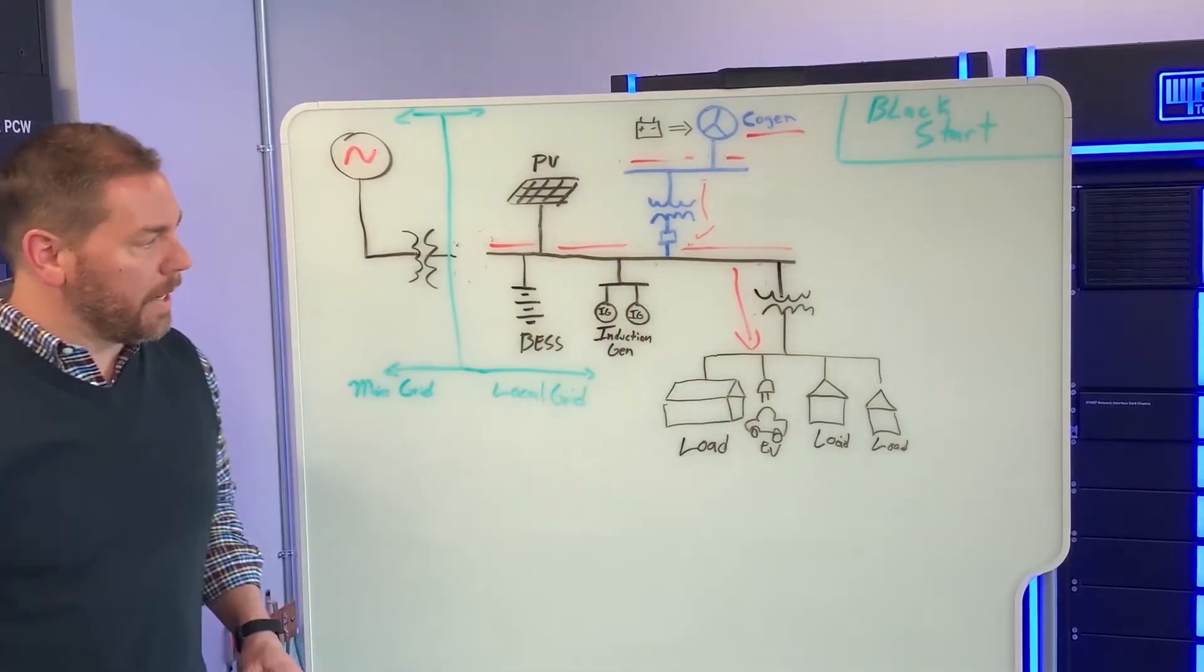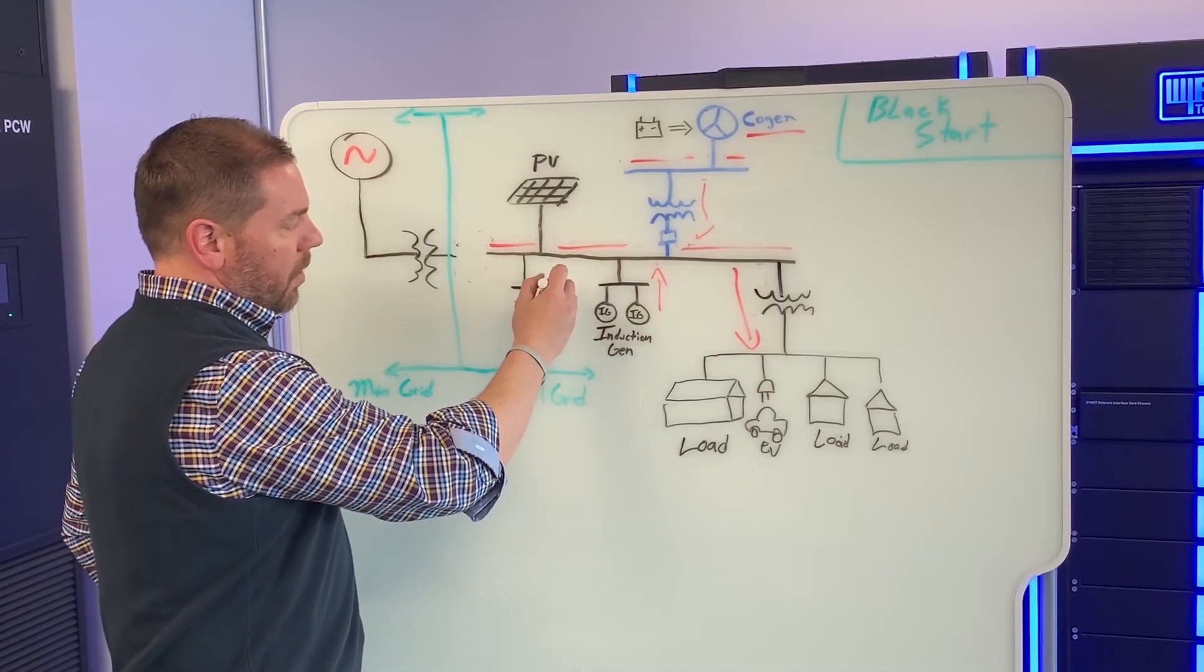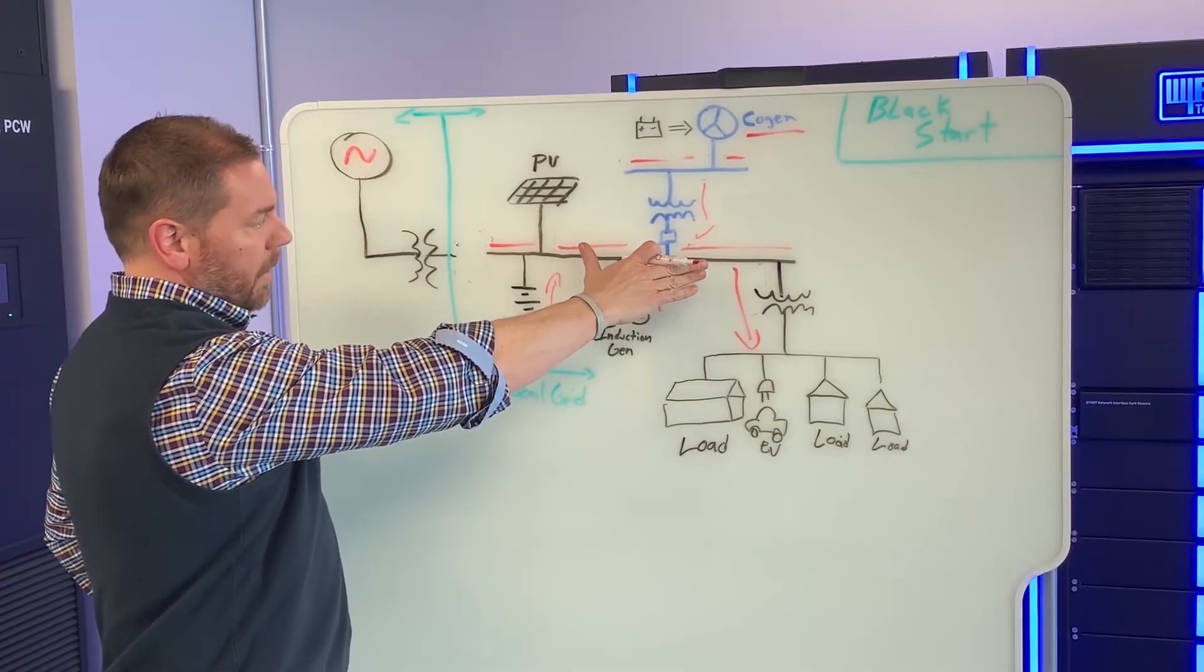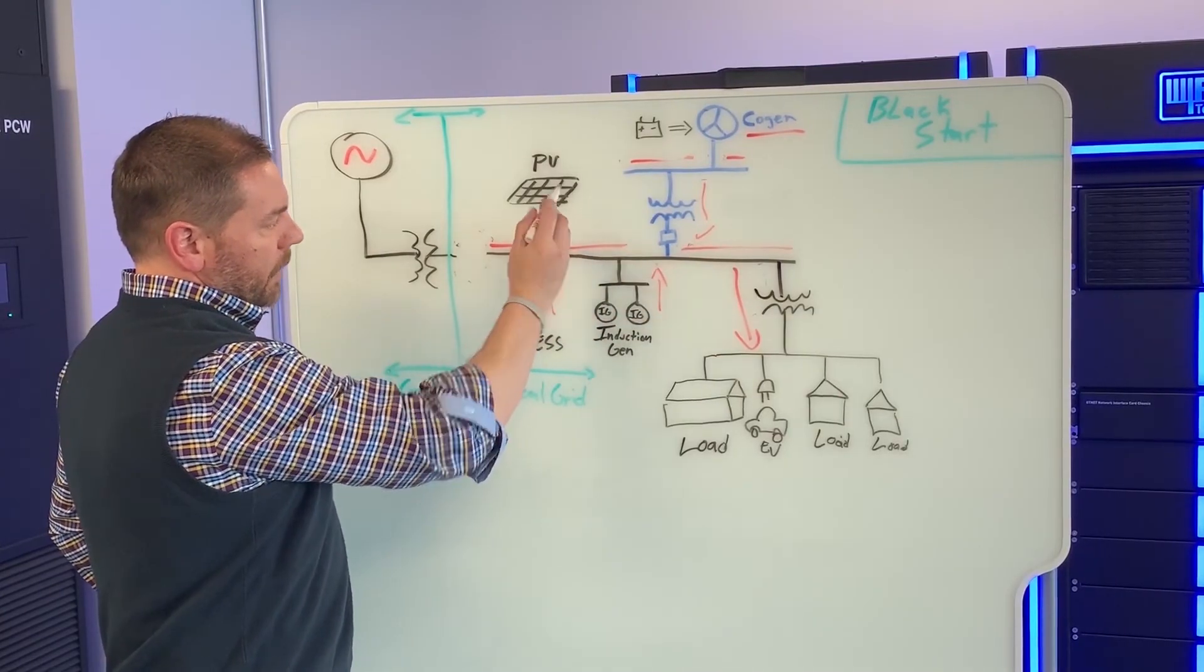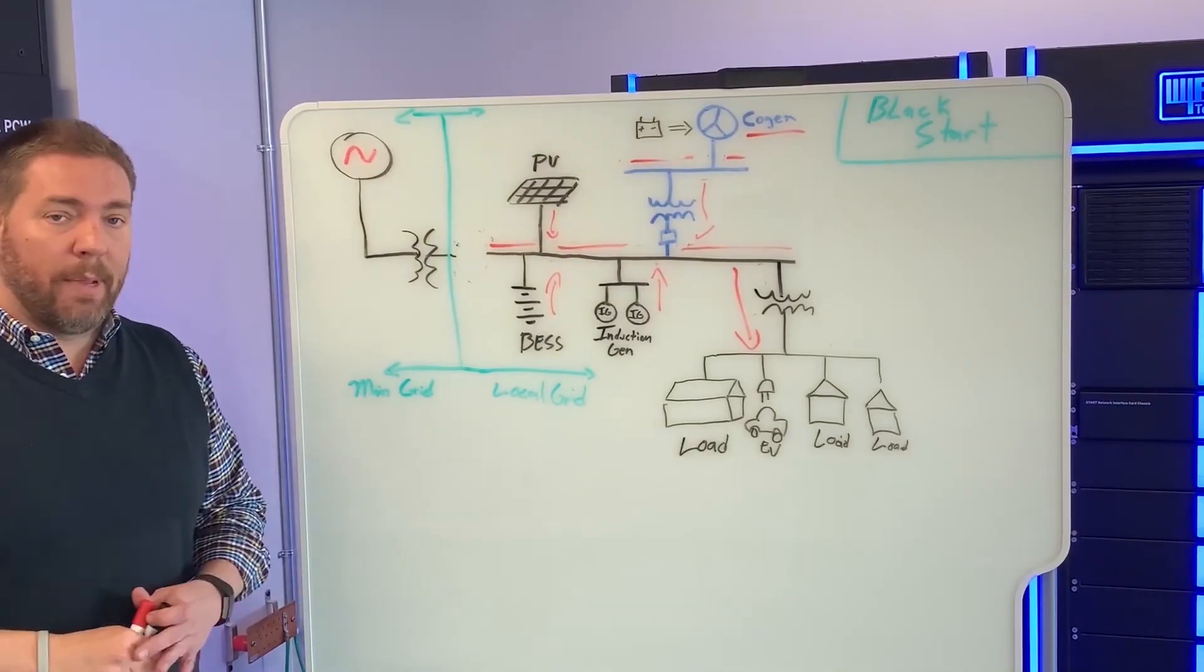And then, at some point, these other DERs can start kicking on because now the Cogen has maintained and formed this grid and can start contributing to the system. And that's pretty much how Black Start works.